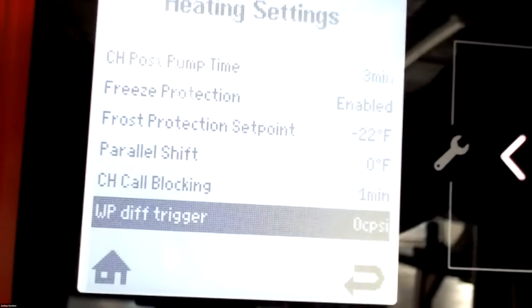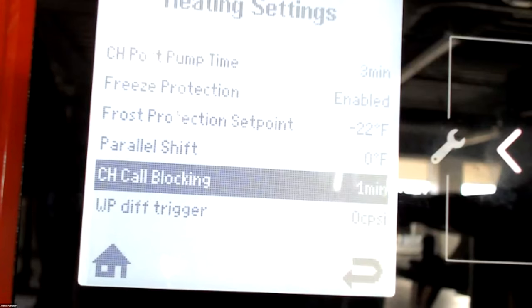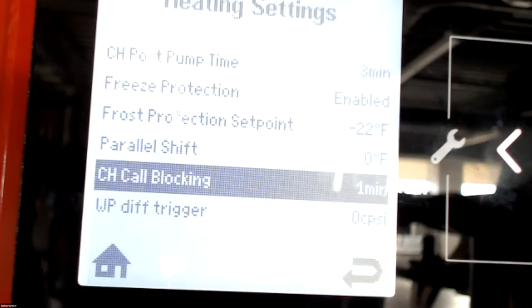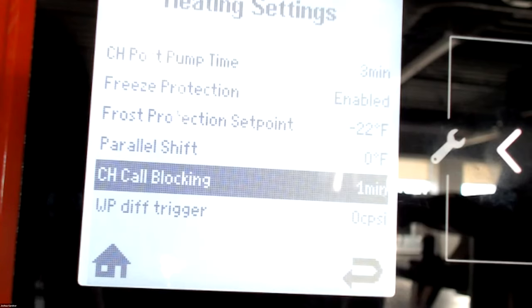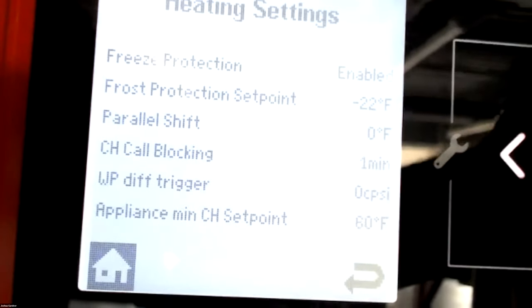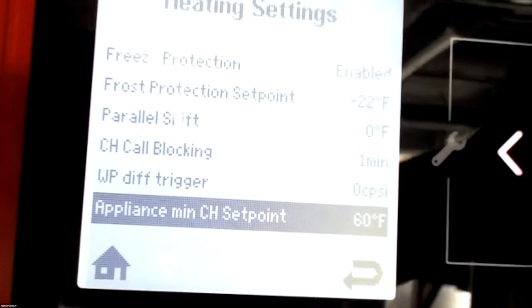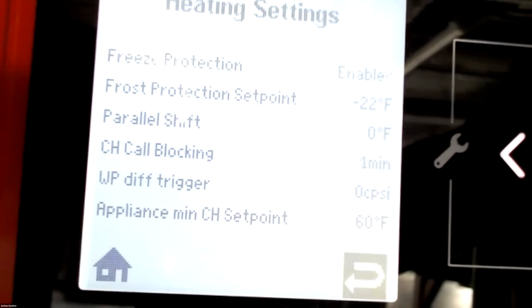CH call blocking. If we wanna prevent this thing from short cycling, if we have small zones and one kicks on, another zone kicks on, as soon as after that one goes out, we can call block that and wait and allow it to post pump, and that might get us our heat out and allow us to get some of that heat into the system and call it and satisfy it. And you're Appliance minimum CH setpoint. Those are the heating settings.